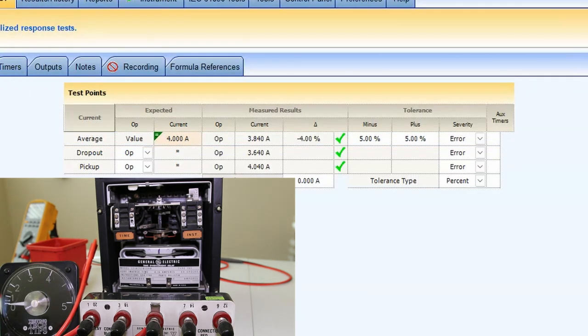There you go — hopefully you can see on the ammeter how it actually operated, because it worked great. This is a much more consistent answer because we're getting the dropout value and the pickup value on the induction unit. It should be more accurate and a little bit more repeatable.